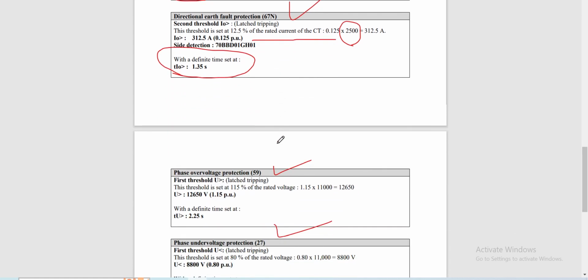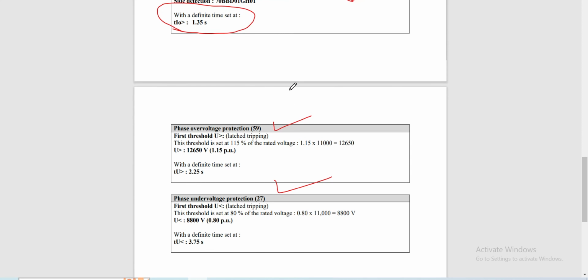Now we're going to discuss the voltage protection. First, our phase overvoltage protection, or the 59 relay. This threshold is set at 115% of the rated voltage. Our voltage here is 11,000 volts.